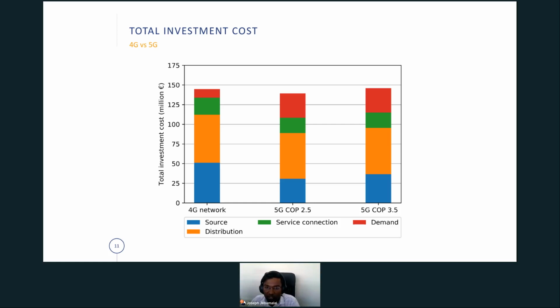And then the network cost is a little bit lower because we use plastic pipes for the fifth generation systems, and for the fourth generation system we use steel pipes. But of course, trenching cost is the more dominant cost, so it is only slightly reduced because of the lower pipe cost for the plastic pipes. But then the investment cost seems to be at the same level if you compare. It depends on the cost assumptions you make, but there is not much difference in the investment cost. But of course, we did not take into account the replacement cost of the heat pumps, because the lifetime of the distributed heat pumps is much shorter, 18 to 20 years, when compared with the heat exchangers.